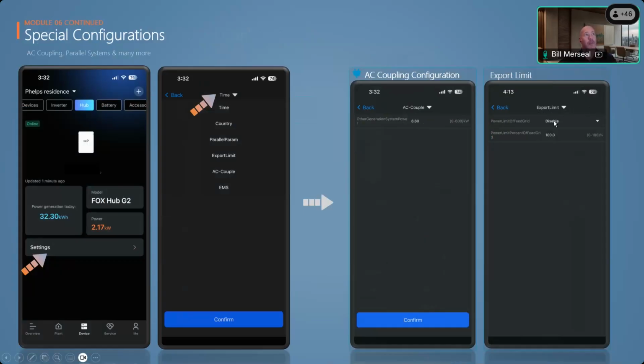Also, we can control if that system exports to the grid or not. If you want to set it up so it does not export to the grid at all, you want to make sure your export limit is set to enable. Then on the power limit percentage of the grid, if you want zero export, you want to put that at 0%. That's a useful feature because some installers use that before PTO. In case of a system where they can't have any export, the system is designed so we can do zero export.